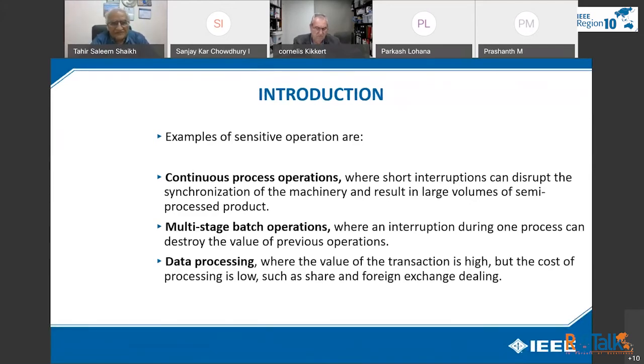A few examples of sensitive operations are continuous process operation. If I have a plant with continuous operation, a slight sag or dip will disturb the whole plant. Multi-stage batch operation, where interruption during one process can destroy the value of a previous operation, the whole plant may stop. Data processing, where the value of the transaction is high, but the cost of the processing is low, such as share and foreign exchange dealings.